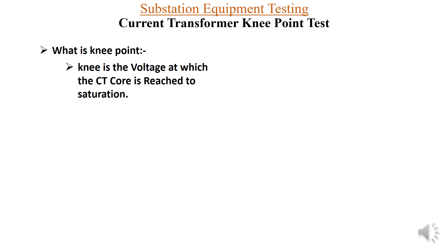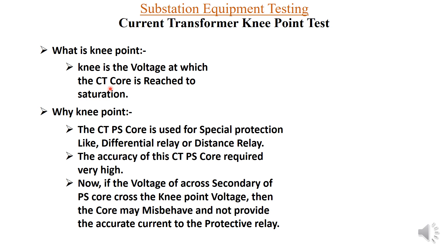Let us understand what is a knee point. The knee point is the voltage at which the CT core will start to saturate. Beyond this knee point voltage, the CT core will start to saturate. That point at which it starts to saturate is called the knee point.